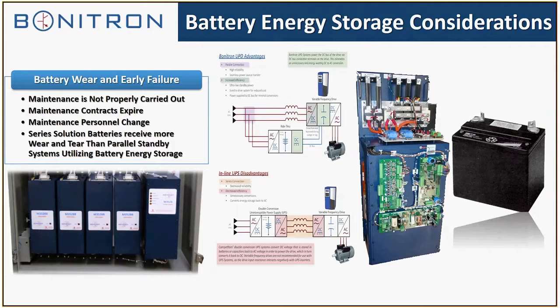Okay, battery energy storage considerations. After dealing with a lot of end users' aggravation with batteries, one thing I find is that once there's a battery service contract or a battery maintenance program in place, it really depends on who's running it and who they're using for the service. You walk in, and they want to know why the UPS didn't work. Well, you go and find out that the battery maintenance wasn't carried out.